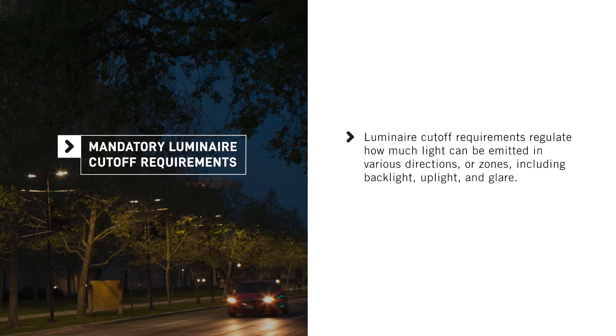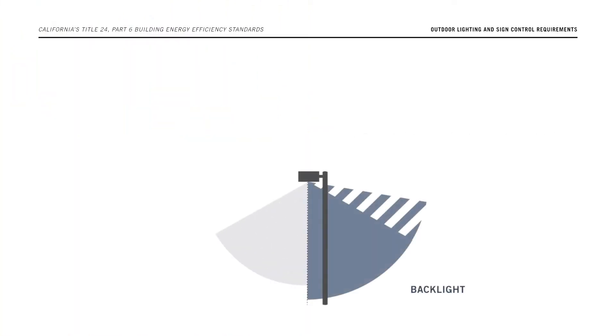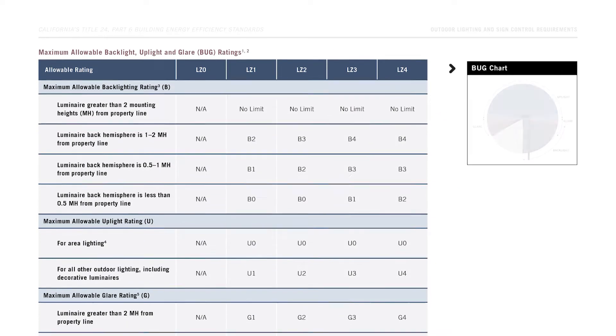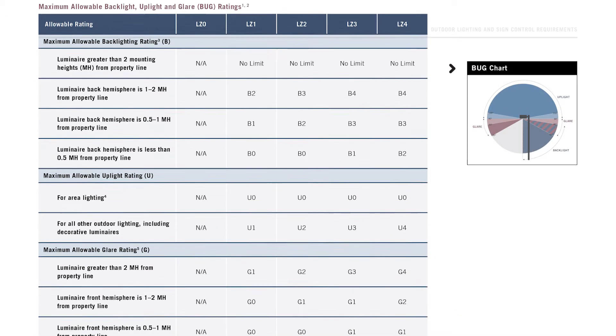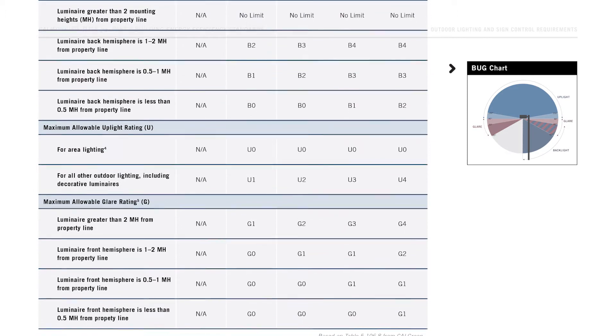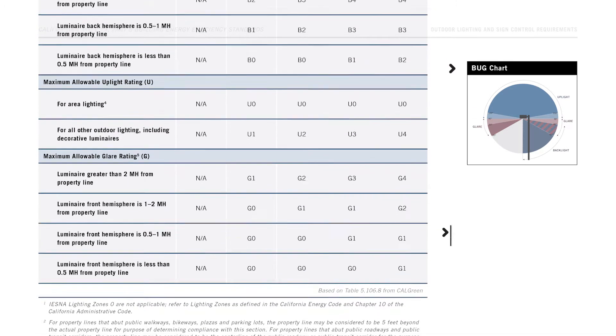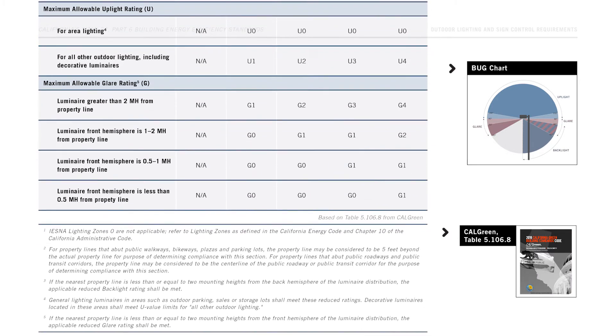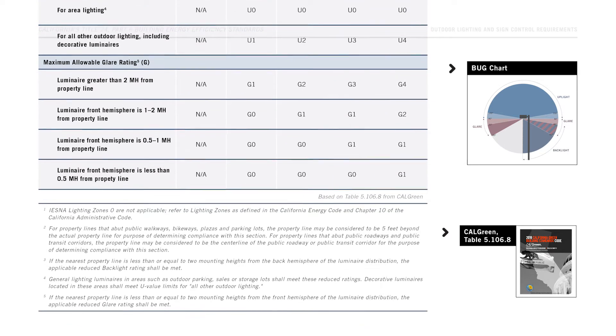Now let's talk about the mandatory requirements pertaining to luminaire cutoff and the exceptions. Luminaire cutoff requirements regulate how much light can be emitted in various directions or zones, including backlight, uplight, and glare. Many types of outdoor lights must comply with these cutoff requirements, which are collectively referred to as BUG requirements. The Energy Code's BUG requirements specify maximum zonal lumens and only apply to outdoor lights rated 6200 initial lumens or more. Specific requirements are provided in Title 24, Part 11, Section 5.106.8, also referred to as the CalGreen Code.